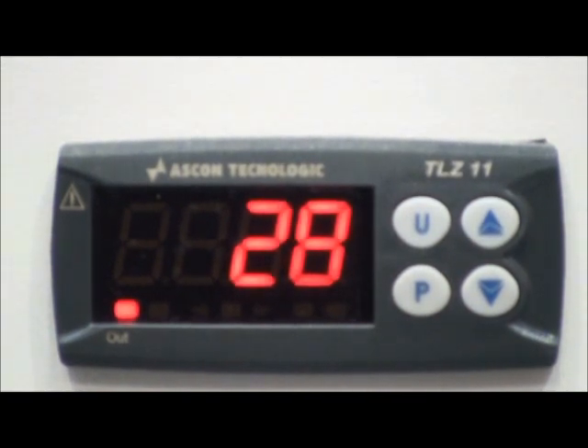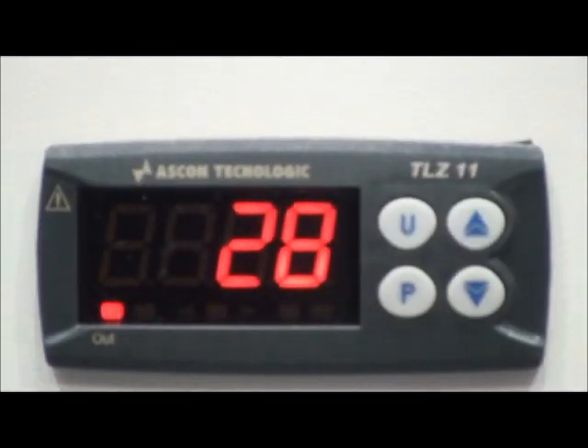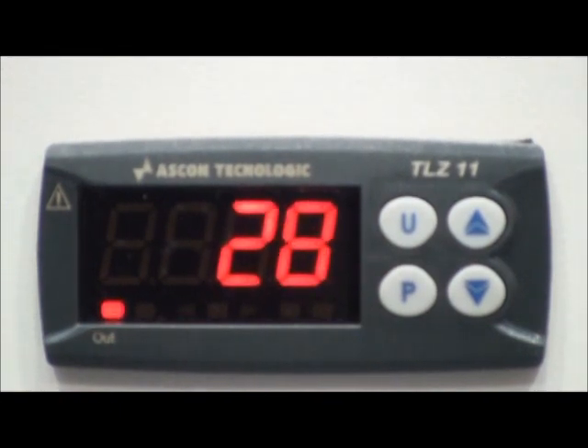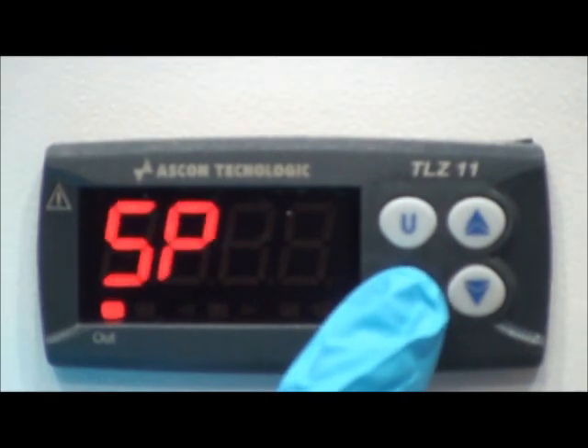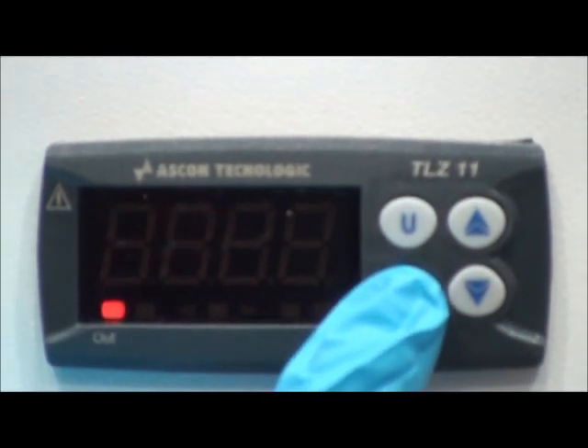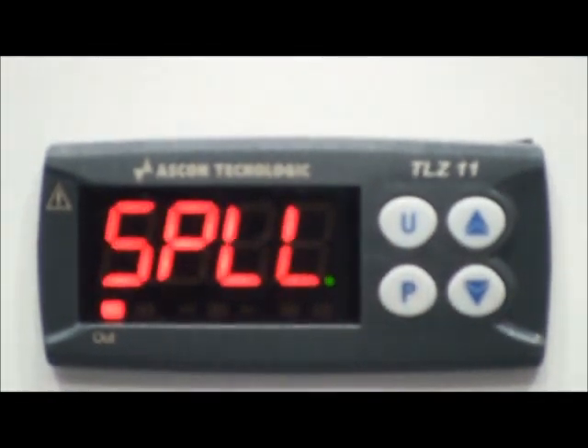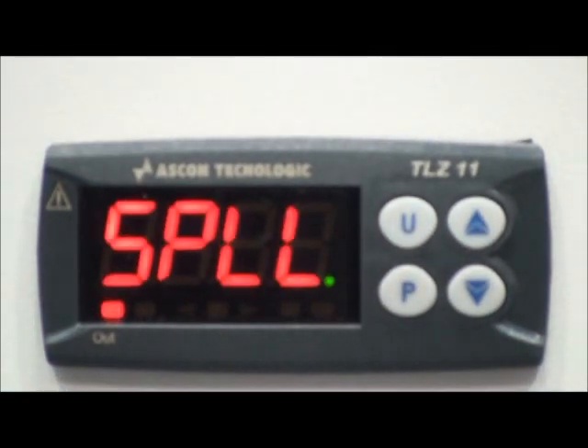We're now going to look at the calibration, which is an engineer operation. The timer is a multi-function device. A number of features are used, but some aren't. So we're going to run through the ones that are now. To access the menu, you press the P key for more than 5 seconds, and you see the first option is the set point lower limit. This is where you want the hot plate to switch off. To access this, you press P, and at the moment it's set for 100. To accept that, you press P again.